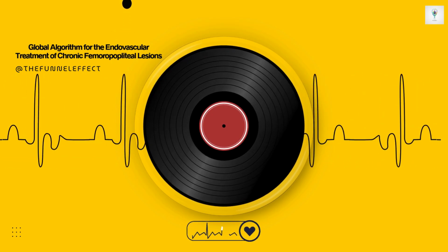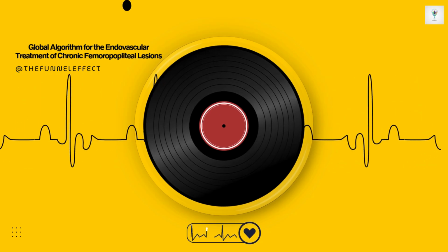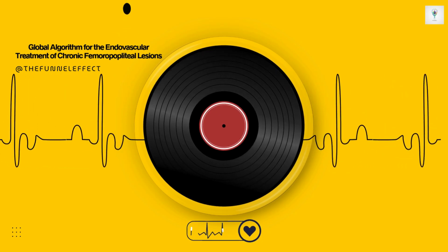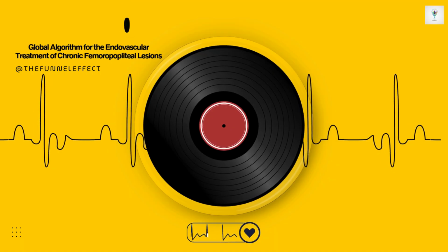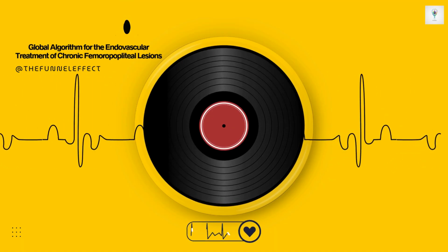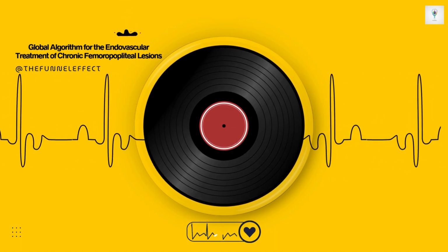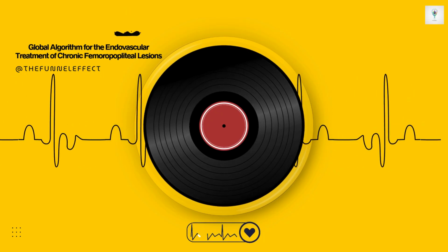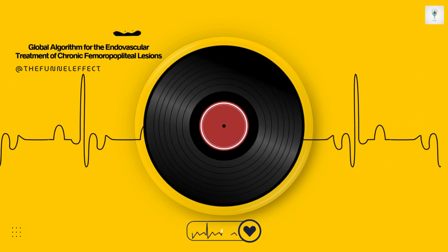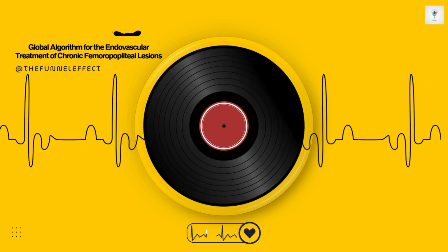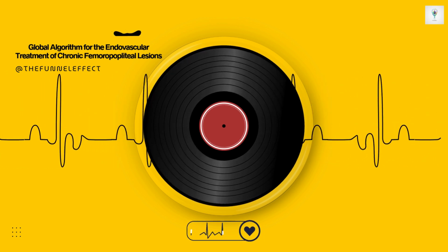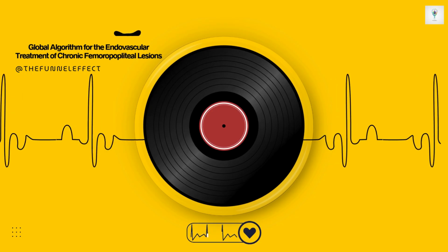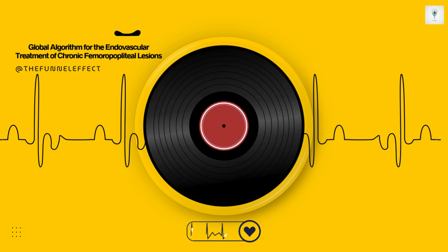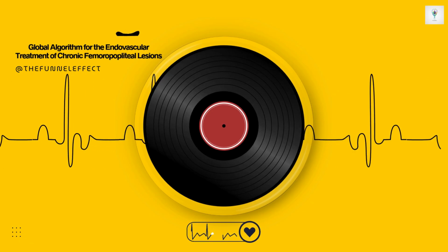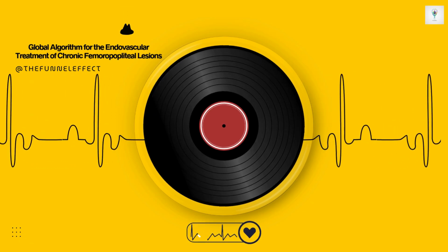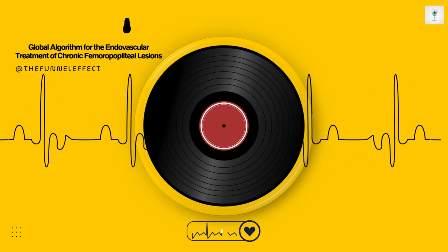It's really quite clever engineering. IVL uses a special balloon catheter with tiny emitters inside. When you inflate the balloon to a low pressure, just enough to touch the vessel wall, maybe 4 atmospheres, you activate these emitters. They generate localized high-frequency sonic pressure waves. Now, these waves travel through the soft tissue, the plaque, the normal vessel wall, without really affecting them much. But when they hit the hard, brittle calcium deposits, they create microfractures. They crack the calcium. So it's selective. It targets the hard stuff.